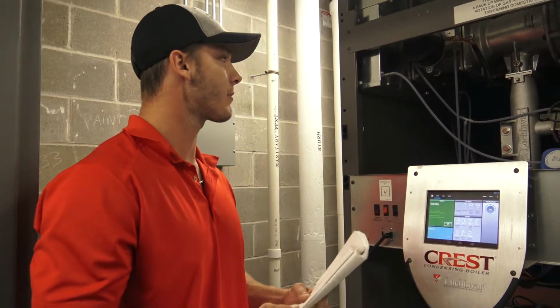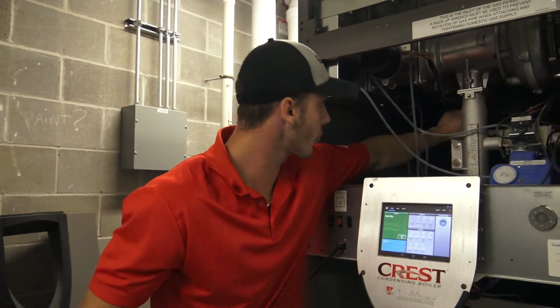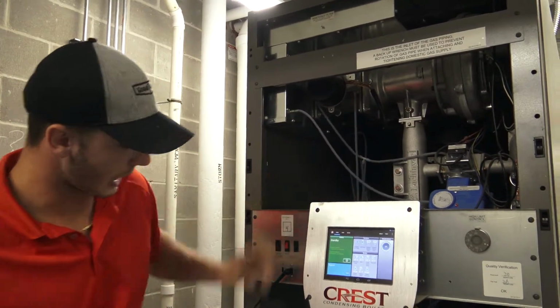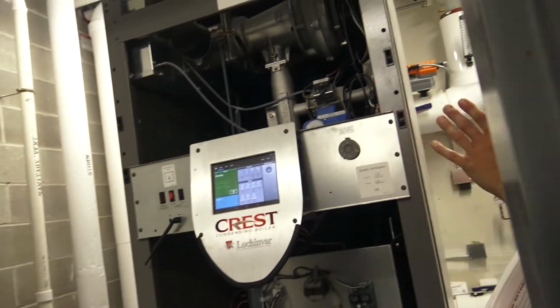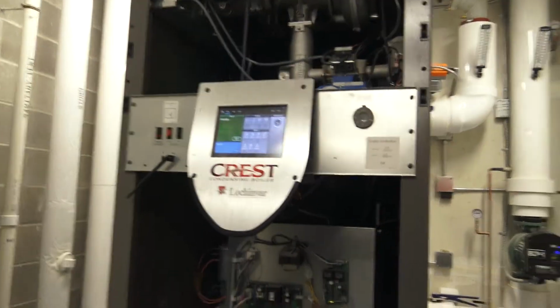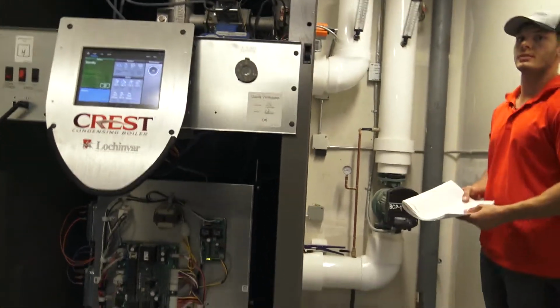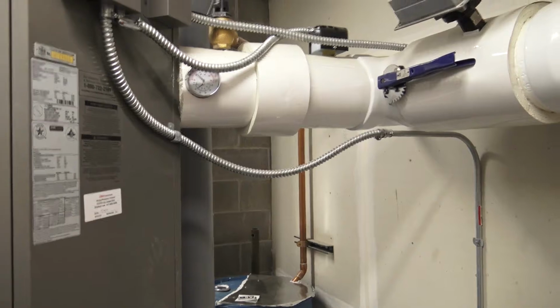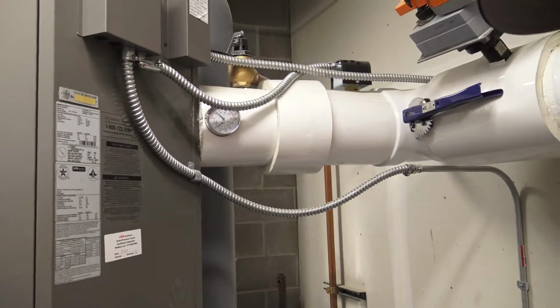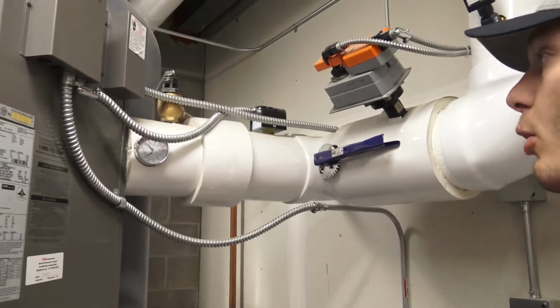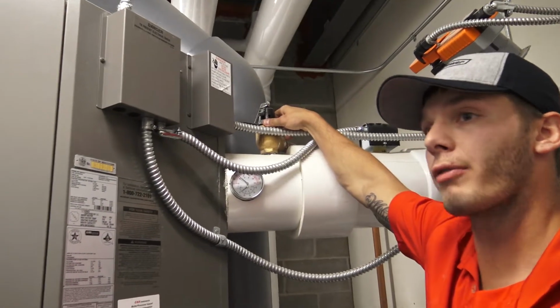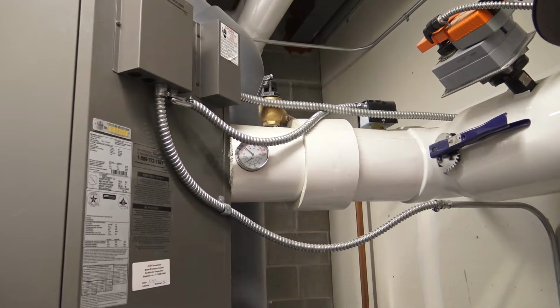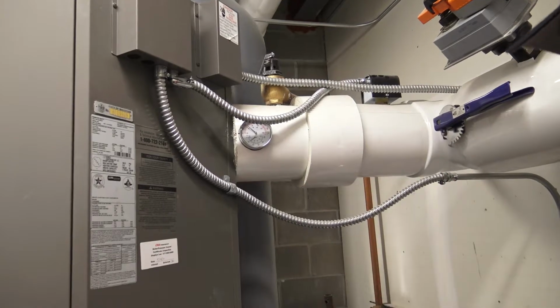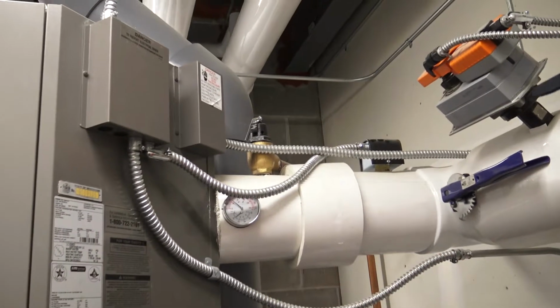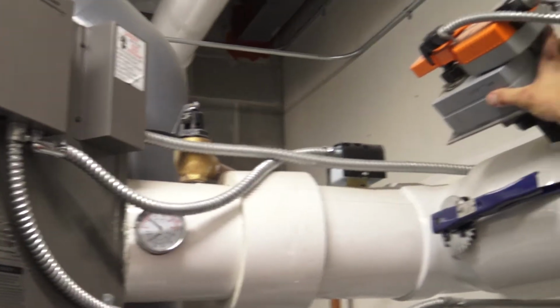I'm going to point out some more safeties. Right here is going to be your outlet temperature. On the bottom, on the inside, if you guys want to sneak around back here, there's some more safeties on the back. Hey, come on in. We have a flow switch right here. Without flow, obviously the boiler is not going to fire. You will get a flow alarm. It'll say no flow. Relief valve: if the boiler exceeds pressure under any circumstance, that relief valve will blow. On top of that, you have a temperature sensor right here. You have your isolation valve right here.